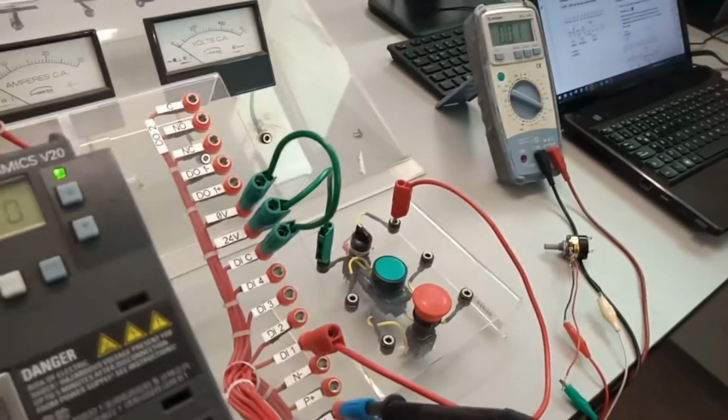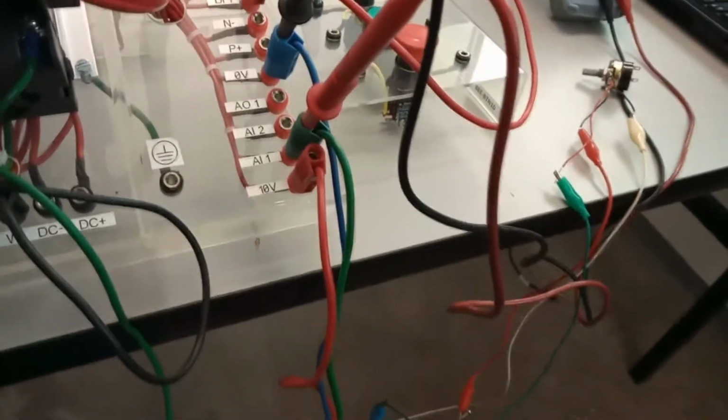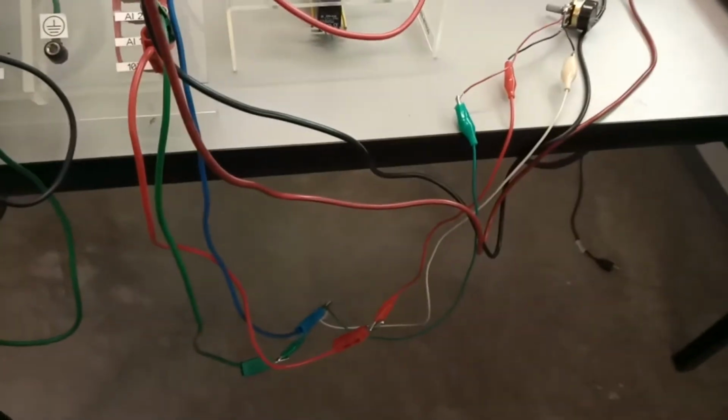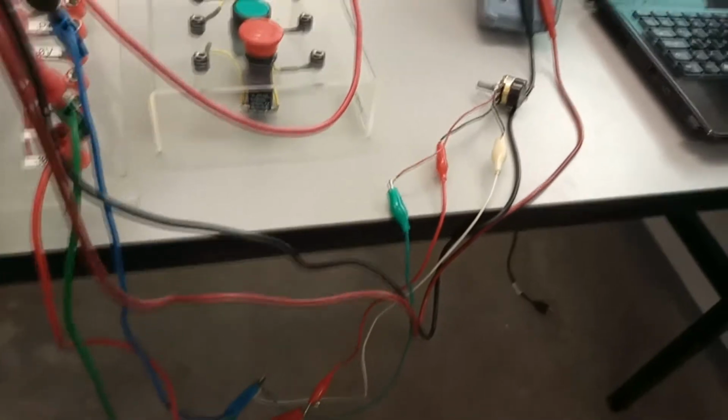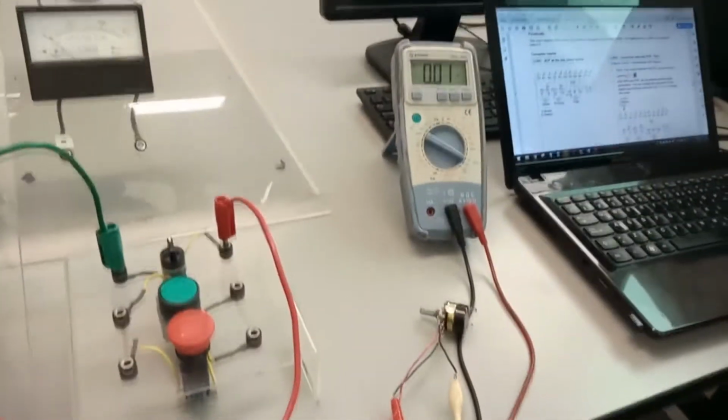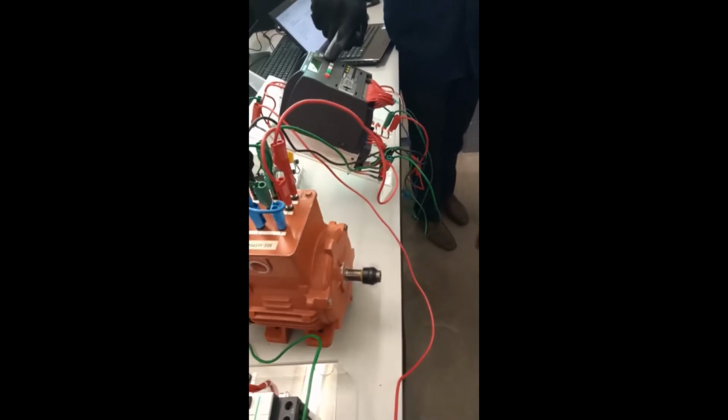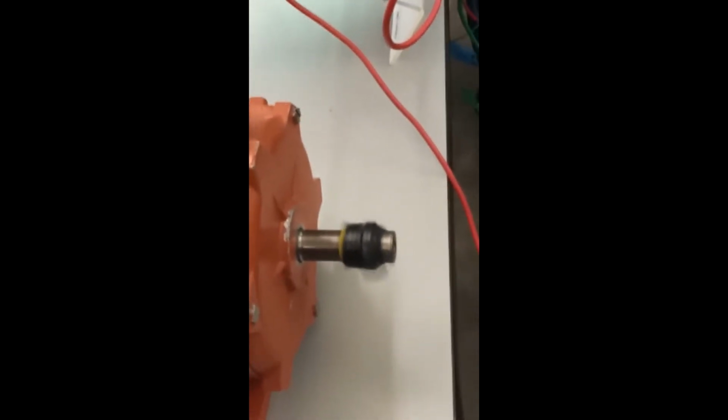The connection was the following. The disconnector was connected to the three-phase signal, and the output of the disconnector was connected to the VFD, but just two lines. Internally, the VFD, with the use of different electrical and electronic devices, generates a three-phase signal as an output, and this output was connected to the motor.